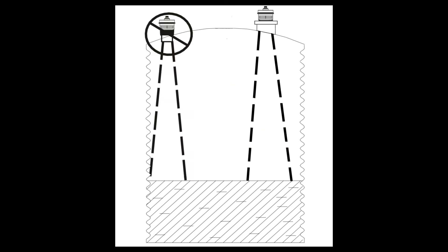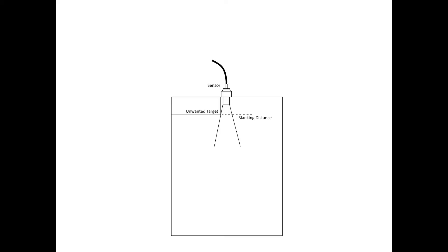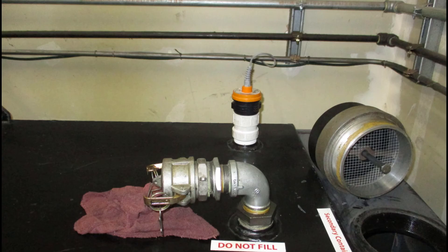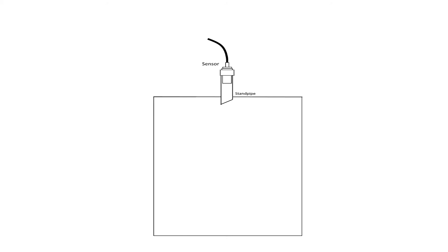Avoid mounting the sensor next to the tank wall, as this may inadvertently be seen as a target by the sensor. The distance from the sensor to the closest possible target should always be further than the blanking distance of the sensor. In applications where headroom does not allow this, a standpipe may be used to mount the sensor above the tank. The standpipe should be smooth and straight with no joints, burrs, or obstructions. If possible, the diameter should be one-half the length.